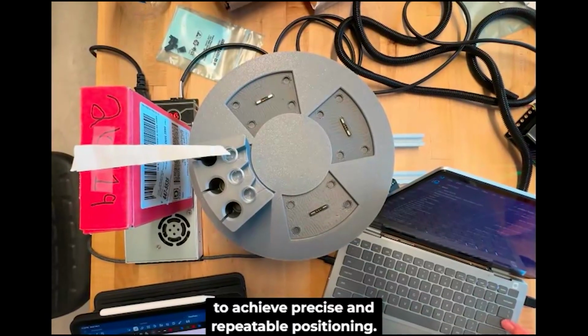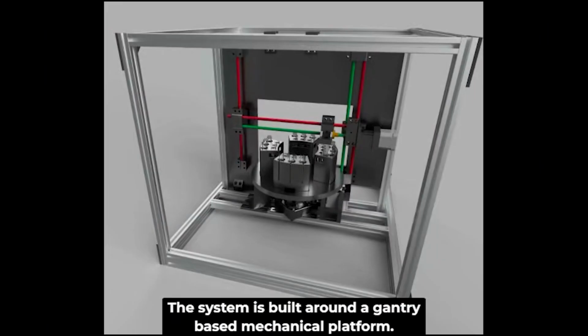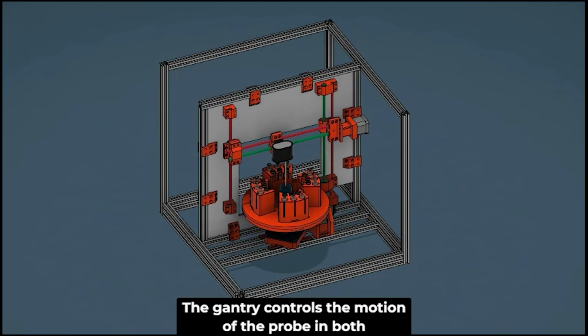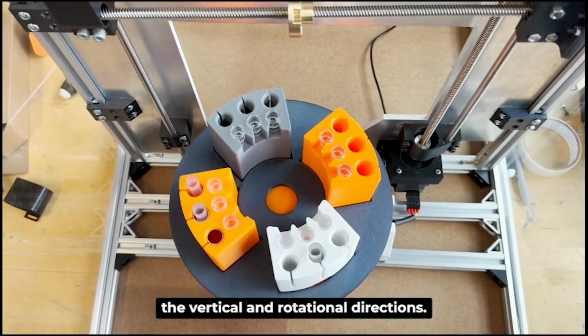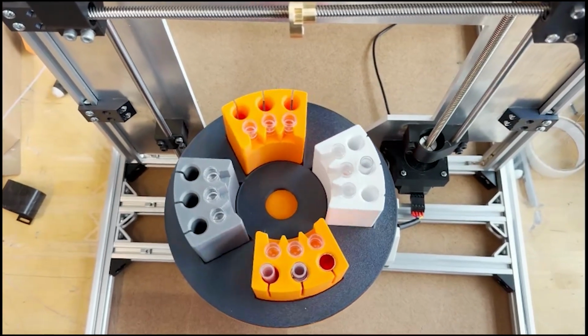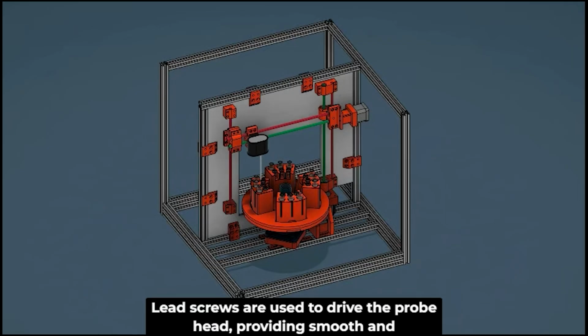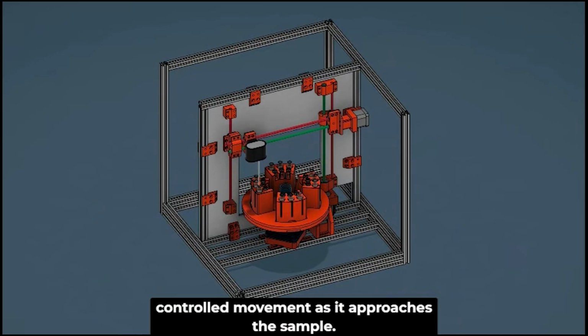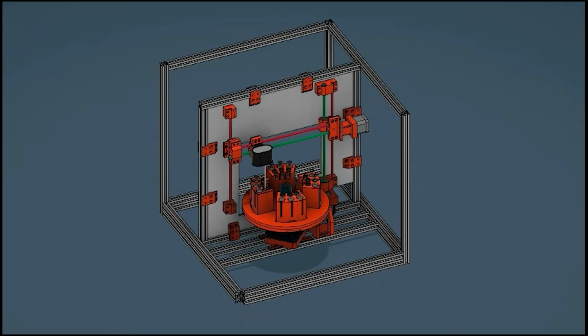To achieve precise and repeatable positioning, the system is built around a gantry-based mechanical platform. The gantry controls the motion of the probe in both the vertical and rotational directions. Lead screws are used to drive the probe head, providing smooth and controlled movement as it approaches the sample.